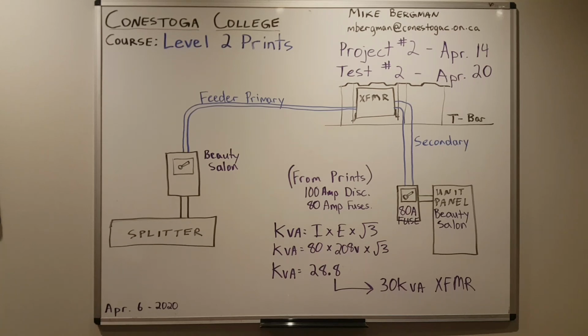There is not a 28.8 kVA transformer. That's not a standard size. The next standard size is 30 kVA. So I would install 30 kVA above the ceiling space in my beauty salon. And now the next thing we'll look at is, how do I size my primary conductors and my feeder for the primary of the beauty salon? And the beauty salon is our example. Now the secondary raceway and the secondary conductors, that will be what the print has currently listed.